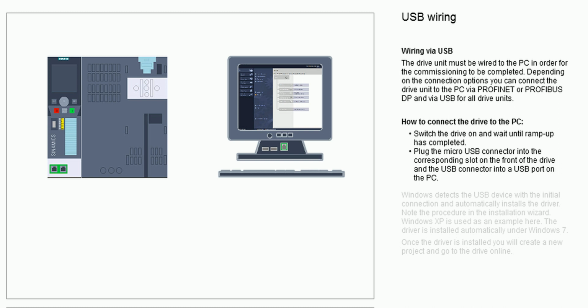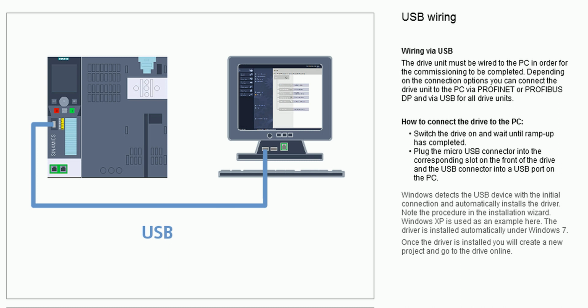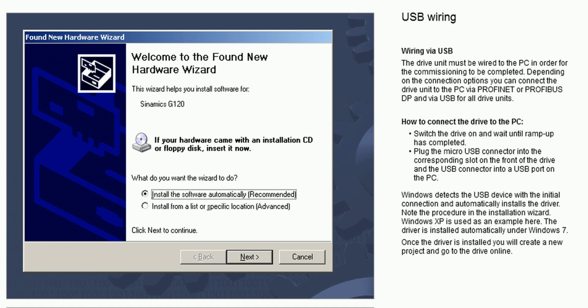Switch the drive on and wait until ramp-up has completed. Plug the micro USB connector into the corresponding slot on the front of the drive and the USB connector into a USB port on the PC. Windows detects the USB device with the initial connection and automatically installs the driver. Note the procedure in the installation wizard. Windows XP is used as an example here. The driver is installed automatically under Windows 7. Once the driver is installed, you will create a new project and go to the Drive Online.